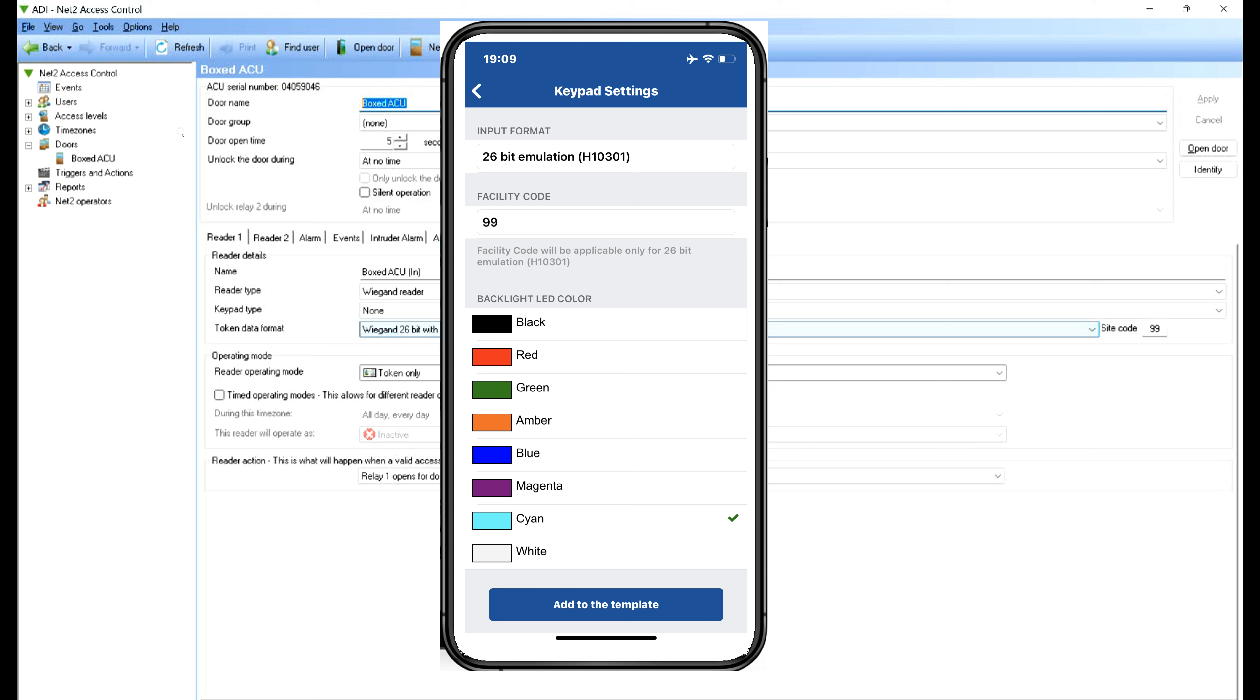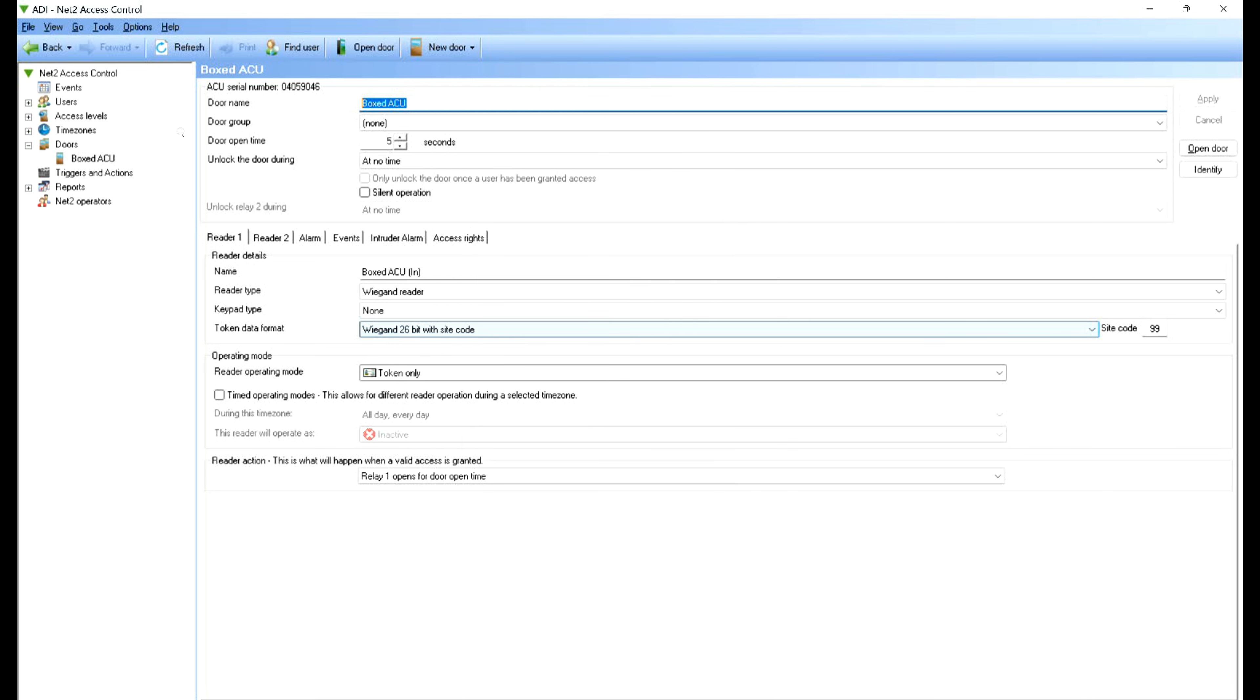So that means it's going to send the information through with a leading site code of 99. The HID reader works by when you type in the five-digit code, it waits till you've typed in that fifth digit and then it sends it to the ACU. So the ACU is just looking for one burst of information.